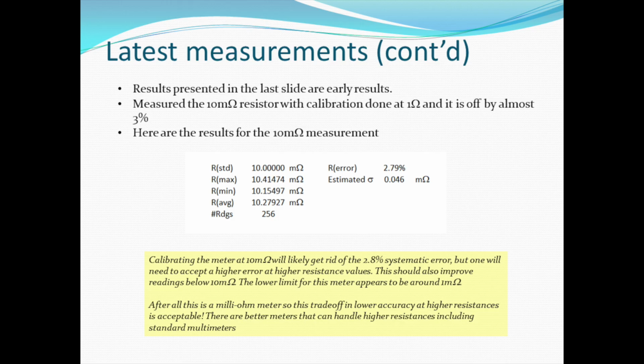So calibrating the meter at 10 milliohm, I can most likely get rid of this 2.8% of systematic error, but we'll still need to accept a higher error because of this. Of course, it's calibrated at 10 milliohm. At 1 ohm, it's going to be worse, but I think that's okay because this is really targeted for milliohm measurements. So I would like to make sure I target this calibration also at a low resistance value. So I think that's the next step to do.